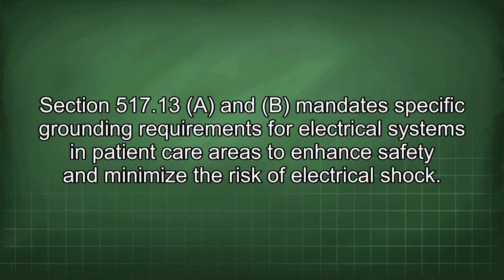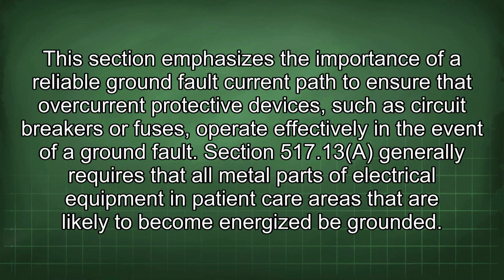Section 517.13 A and B mandates specific grounding requirements for electrical systems in patient care areas to enhance safety and minimize the risk of electrical shock. This section emphasizes the importance of a reliable ground fault current path to ensure that overcurrent protective devices, such as circuit breakers or fuses, operate effectively in the event of a ground fault.